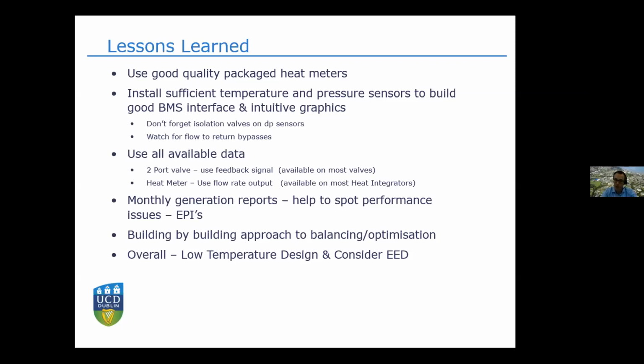So, using all available data. We have two-port valves on our buildings, but just because you tell them to go to 50% doesn't mean they will, and just because you tell them to close doesn't mean they will. All these valves have a positional feedback signal which isn't always connected, so that information is just sitting there waiting to be used. We wire that in too, so we know when you tell a valve to go to 10%, it actually does, or you can see a valve passing, or not closing when it should.